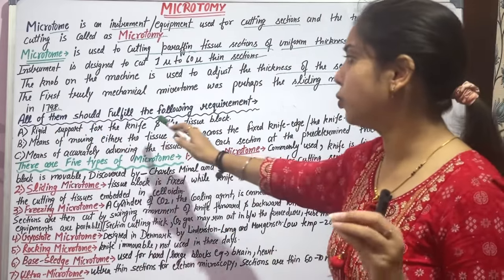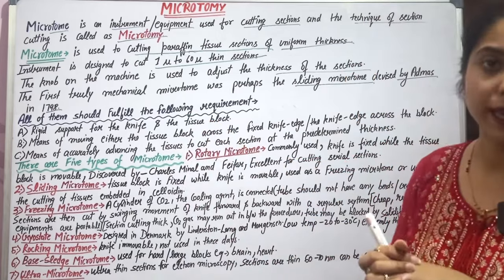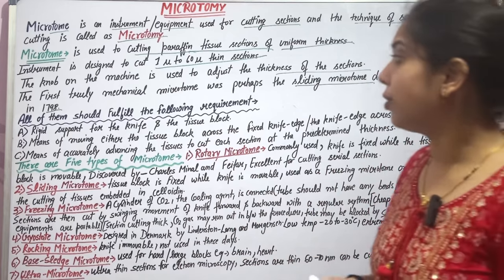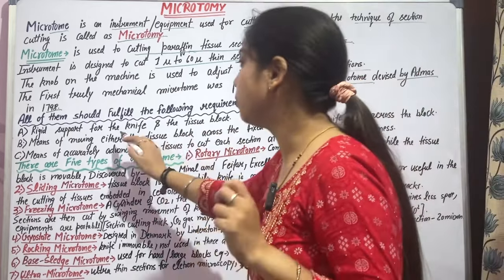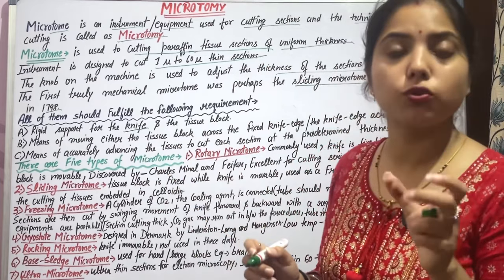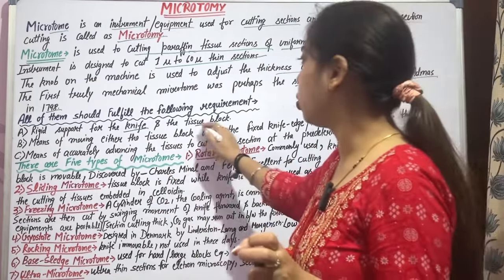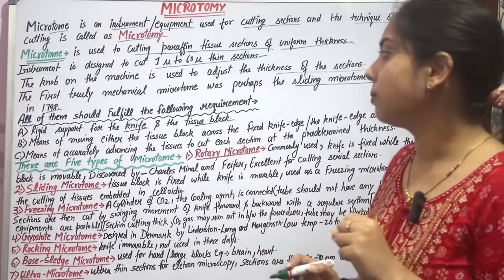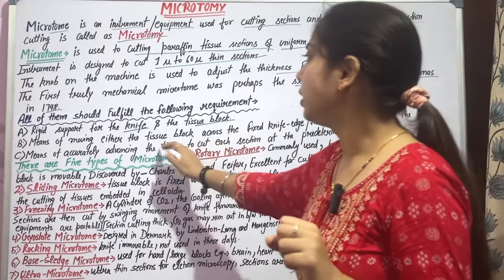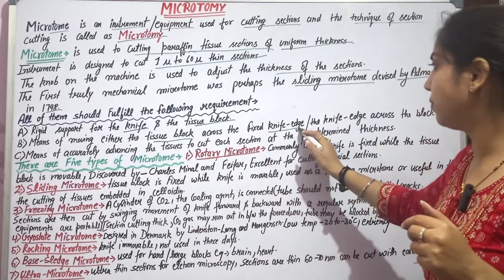All microtomes should fulfill the following requirements. The microtome should have rigid support for the knife and the tissue, so that it can cut the tissue block properly. There must also be means of moving either the tissue block or rotating it across the fixed knife edge.